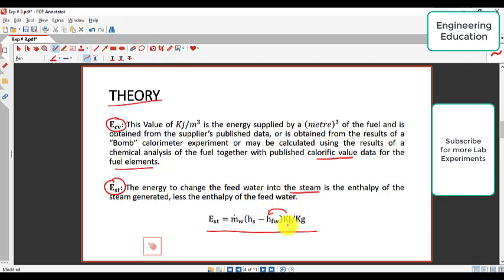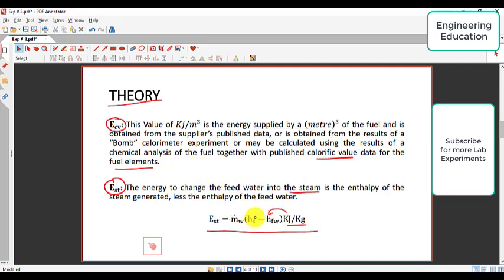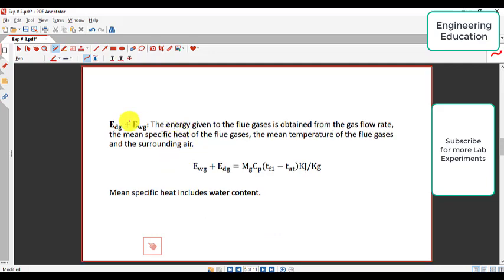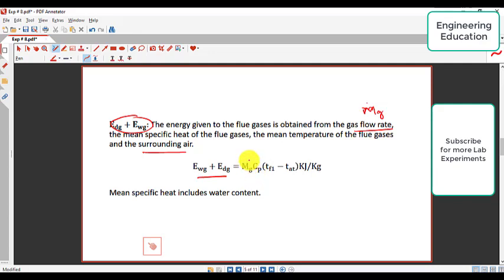The unit of mass flow rate of water is kilogram per second. HS is the enthalpy of steam and HFW is the enthalpy of the feed water. EDG and EWG are the energies given to the flue gases, obtained from the gas flow rate. We must know the gas flow rate, represented by M-dot-G, the mean specific heat of the flue gases, the mean temperature of the flue gases, and the surrounding air temperature.